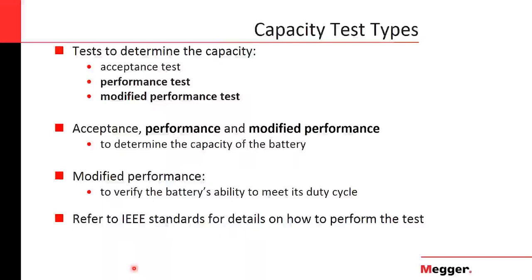There are 3 types of tests that you can run to determine the capacity of the battery. You can do an acceptance test, which is the test that you run at the beginning of the life of the battery, usually 6 months into the installation, or at a certain point before 2 years. Then you can run the performance test, after 2 years, to determine if the battery has started deteriorating, or how the capacity is behaving. The modified performance test is another type of test in which you still calculate the capacity, but you also check that the battery is capable of meeting the duty cycle that you have in the substation.